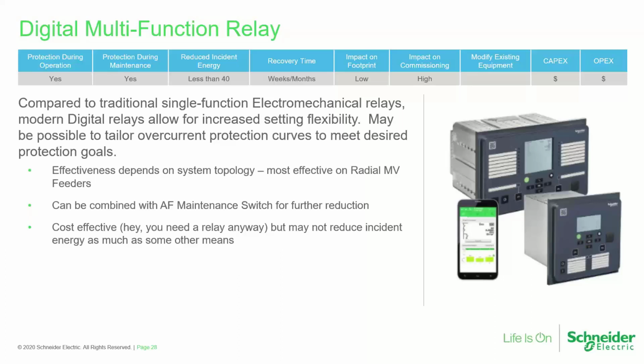I guess probably not too many people are using traditional electromechanical relays, single function overcurrent electromechanical relays right out of the box or right from the beginning these days anymore. But some of the simpler digital relays essentially have the same functionality that those did. But if you step up to the next level, relays that have multiple overcurrent elements, you may be able to tailor your protection curves to get the kind of protection that you want. And the effectiveness may depend on the system topology.